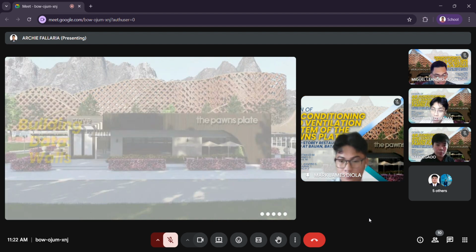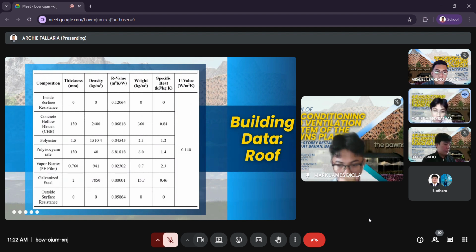And for another building data, we have the roof. The roof is designed to minimize heat transfer, ensuring improved thermal performance and energy efficiency for the building envelope. It is composed of multiple layers, including concrete hollow blocks, polyester, polyisocyanurate insulation, a polyethylene vapor barrier, and galvanized steel, along with allowances for both inside and outside surface resistances. With this, the total thickness of the roof build-up is approximately 304.26 mm with an overall U value of 0.140 watt per meter squared Kelvin, indicating a highly insulated system.